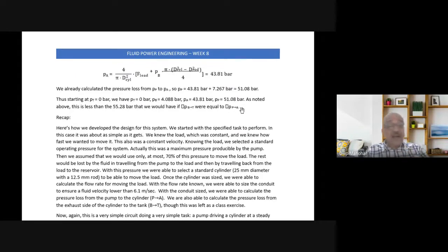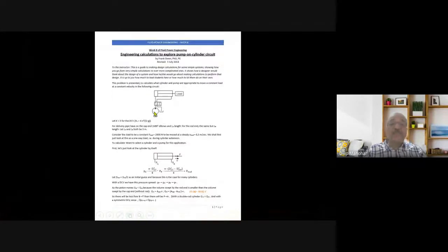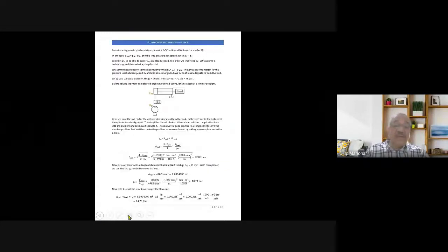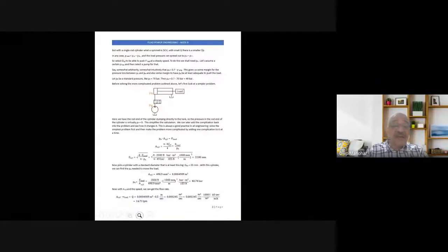So this way, what we are saying is we worked out how to calculate the exact size of the cylinder. What we then did is the exact data of the conduit size, pump pressure, LPM. So now you may be able to select the pump based on exact calculation, slightly on the higher side. Then discharge also, you can keep slightly on the higher side, maybe roughly 5 to 10% extra. And this way we are able to conclude that the parameters given here, we are able to satisfy. So we were able to do everything as per the required data.